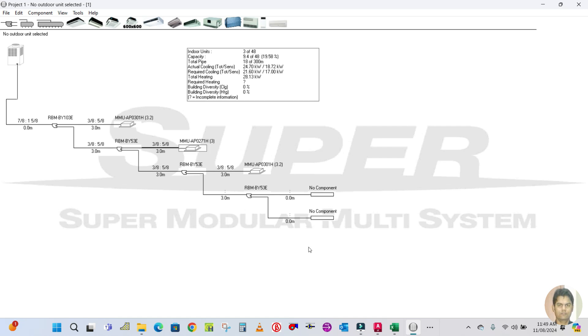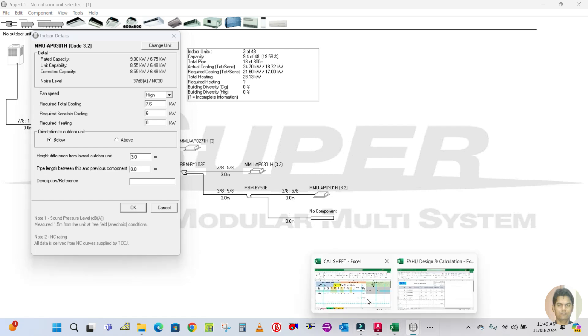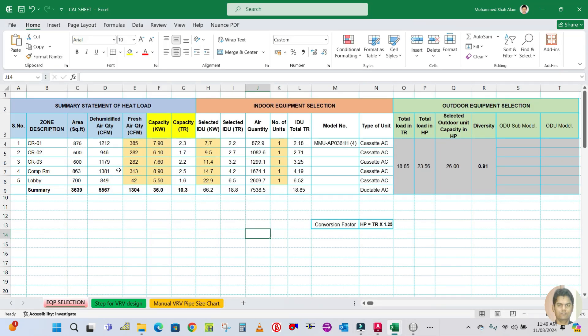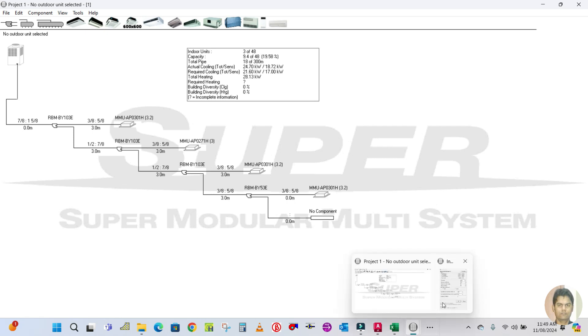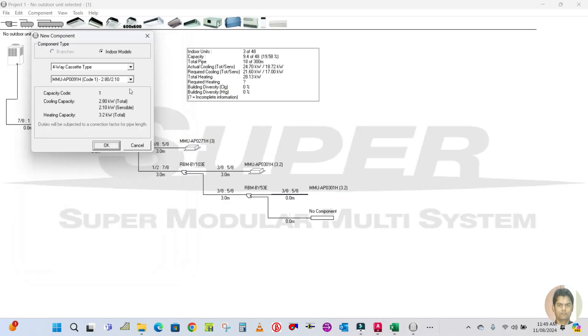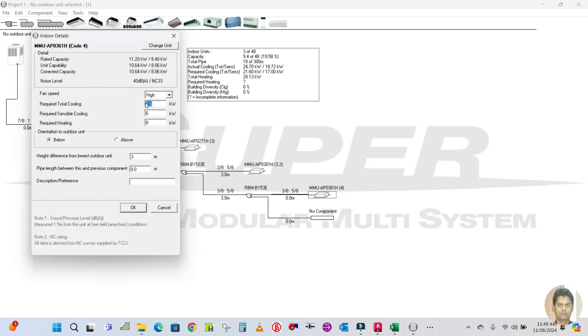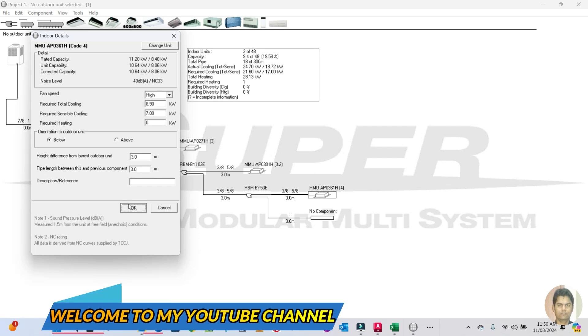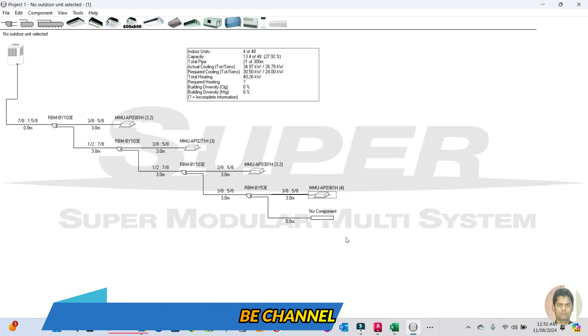Copy this one — classroom 3 — and for the computer room the required capacity is 8.9 kilowatts. Change the unit and go for the 11 kilowatt option. Update the required total cooling capacity to 8.9 kilowatts, sensible to 7 kilowatts. The pipe length between this and the previous component is 3 meters. Click OK.